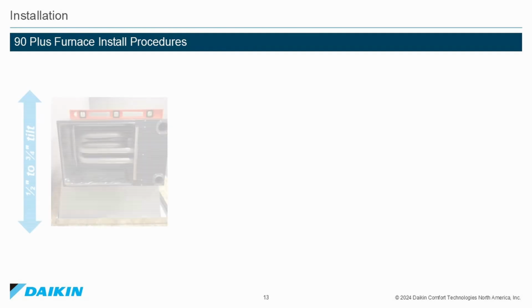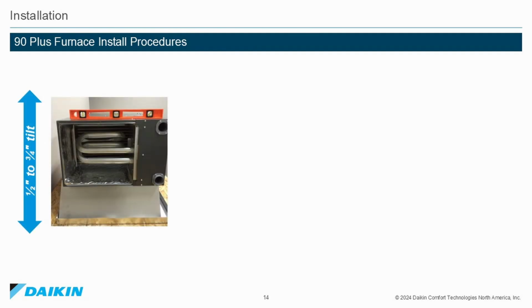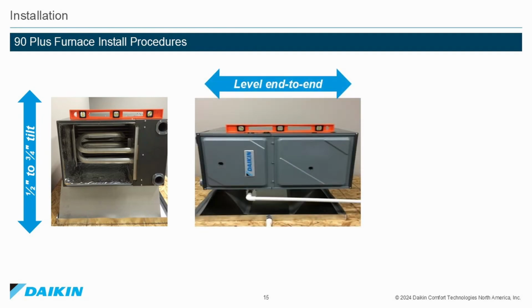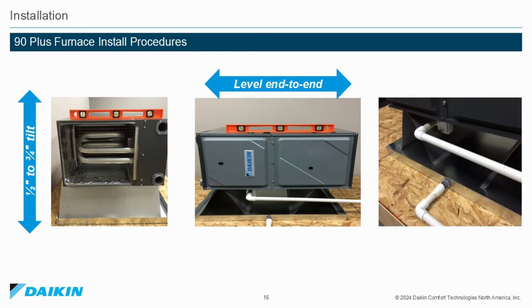90+ furnace install procedures. The furnace should be installed with a 1/2 to 3/4 inch forward tilt for condensate drainage. The furnace should be level from end to end. If the furnace is in an attic or above a finished area, it should have a secondary drain pan installed.